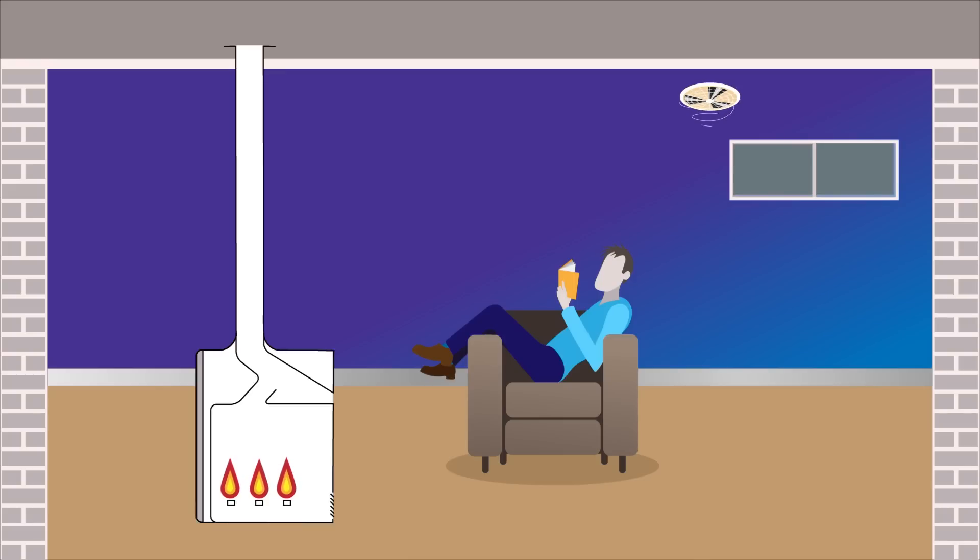A smoke test must be carried out when your gas appliance is off and the flue is cold. Using a smoke match, check that smoke is not drawn away from the appliance draft diverter relief openings or from the appliance combustion air intake.